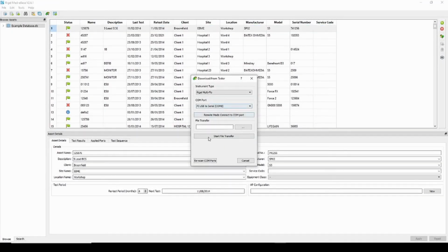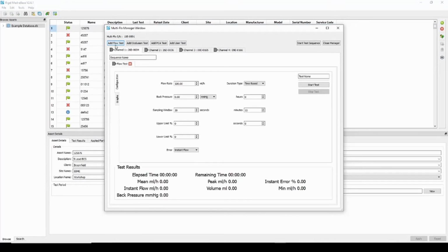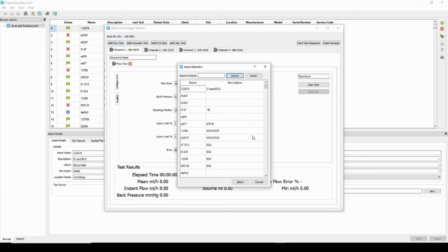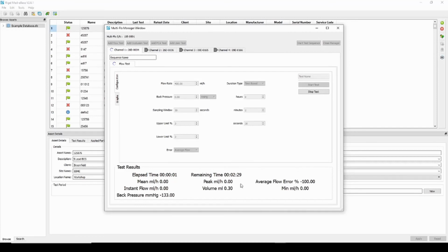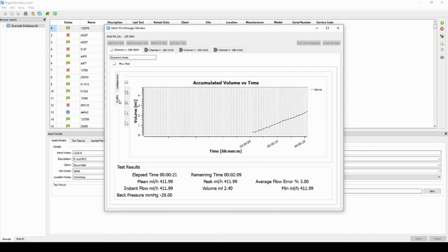So let's do an average flow rate test in Med-eBase. Looking at this, we're changing the error now from volume to average flow. Still got those same upper and lower limits, but with this we can have a look at how the infusion device performs over time. So if the flow is accurate over 2.5 minutes, say, so we're going to run this for 2.5 minutes, and then once that time's elapsed, you can have a look at how the mean flow rate starts to level out and becomes accurate. So you can use it for analysis and looking at the on-screen data in real time.